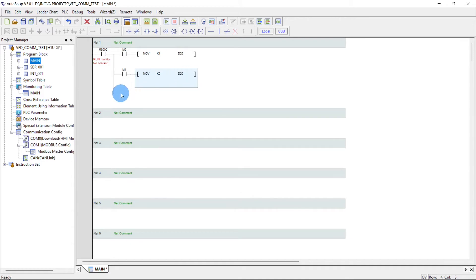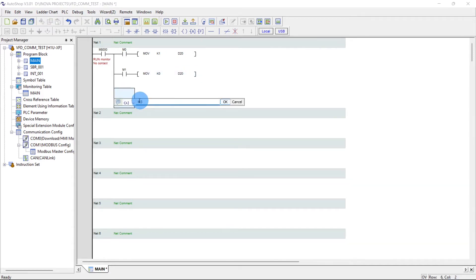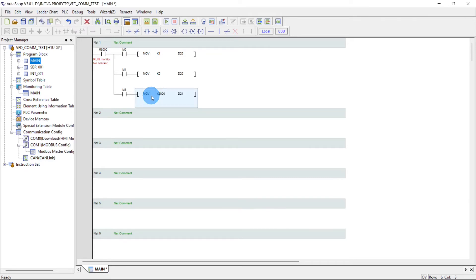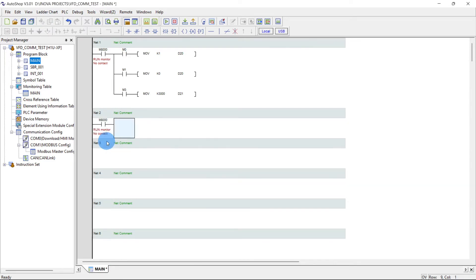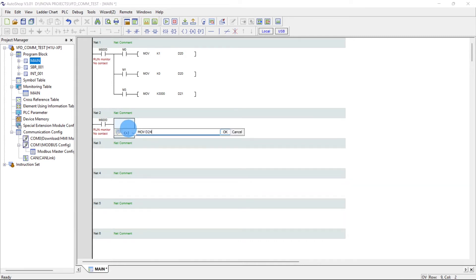And here m3, move k3000 d21. This is the frequency value. Whatever value we move from here goes to the VFD. 3000 is equal to 30 Hertz. Current monitor, move d24 d30. This I am taking just to show you guys the output frequency value.